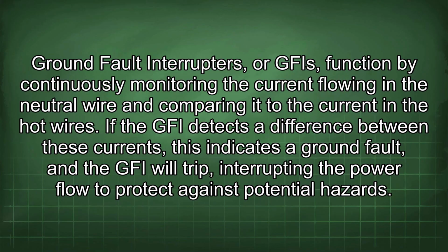Ground fault interrupters, or GFIs, function by continuously monitoring the current flowing in the neutral wire and comparing it to the current in the hot wires. If the GFI detects a difference between these currents, this indicates a ground fault, and the GFI will trip, interrupting the power flow to protect against potential hazards.